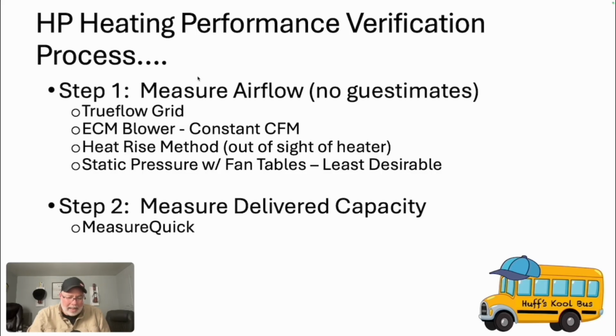If I measure the capacity now as it stands the way it is when I got there, and then I make an improvement and then I test again, I'm able to prove my work. I'm able to show the amount of BTUs I measured when I got here, and the amount of BTUs I measured once I made the correction, and then I can just do some quick math and show you the percentage of change. You can say, you know what, I increased the delivered BTU capacity by X percent, right? So when you uncover a problem, go ahead and still measure the capacity and take that information and then make the correction. That way you're able to show. Because if you go there and you uncover something and then you fix that first, you don't know how much change you were able to get out of that system and how much improvement. And being able to prove our work mathematically is key to helping customers understand and have confidence in your serviceability.